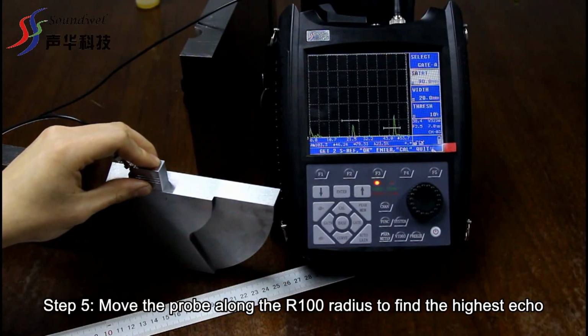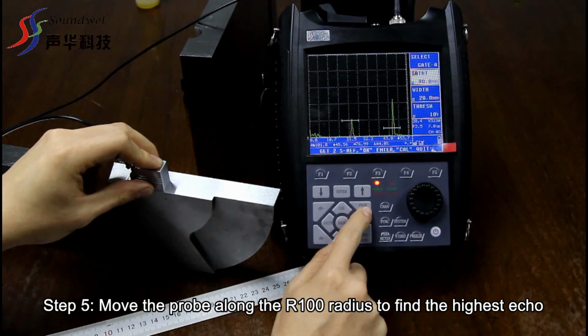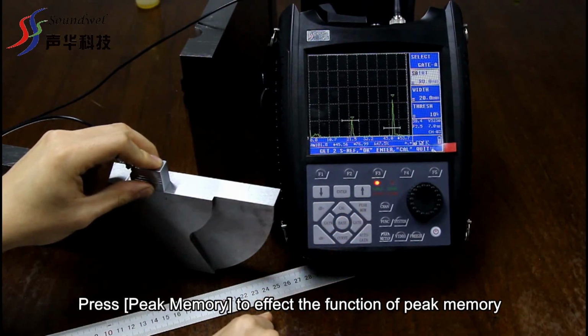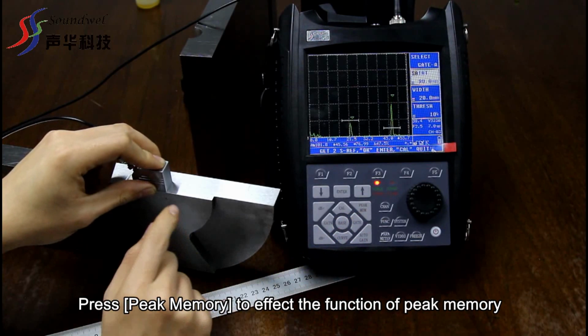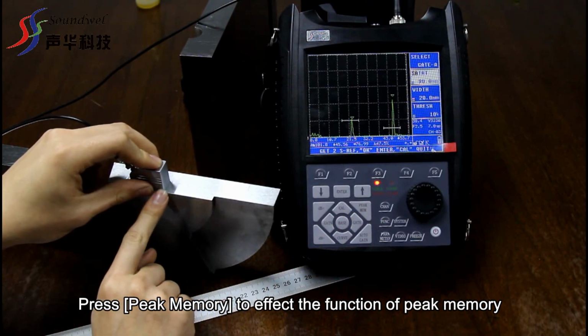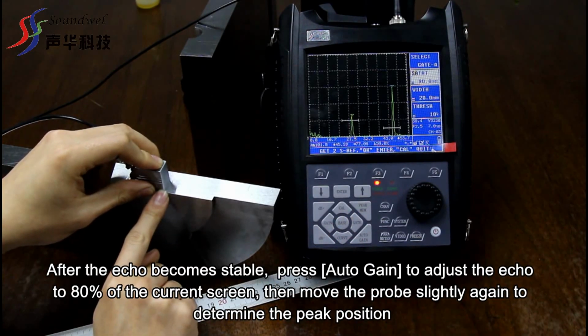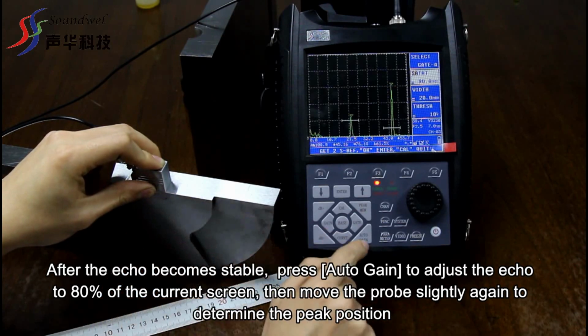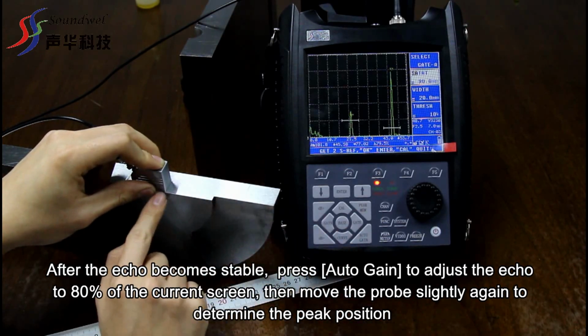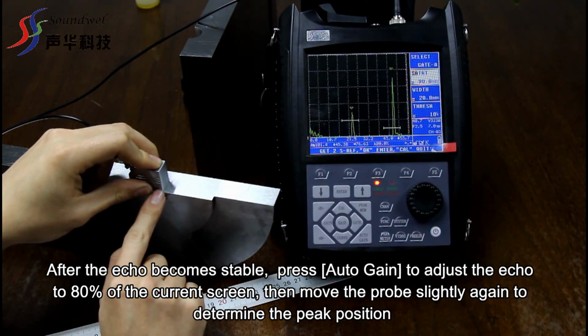Step 5. Move the probe along the R100 radius to find the highest echo. Press Peak Memory to activate the function of peak memory. After the echo becomes stable, press Auto Gain to adjust the echo to 80% of the current screen. Then move the probe slightly again to determine the peak position.